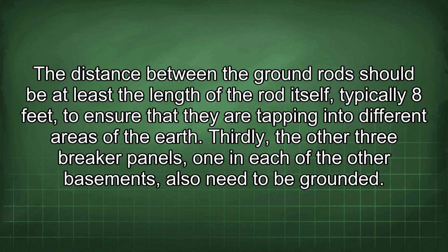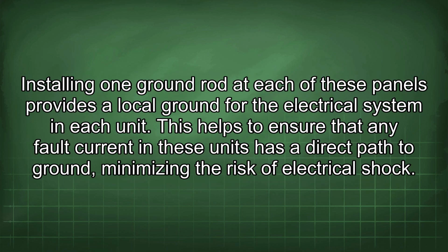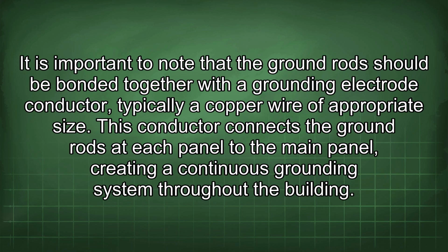Thirdly, the other 3 breaker panels, 1 in each of the other basements, also need to be grounded. Installing 1 ground rod at each of these panels provides a local ground for the electrical system in each unit. This helps to ensure that any fault current in these units has a direct path to ground, minimizing the risk of electrical shock. It is important to note that the ground rods should be bonded together with a grounding electrode conductor, typically a copper wire of appropriate size.